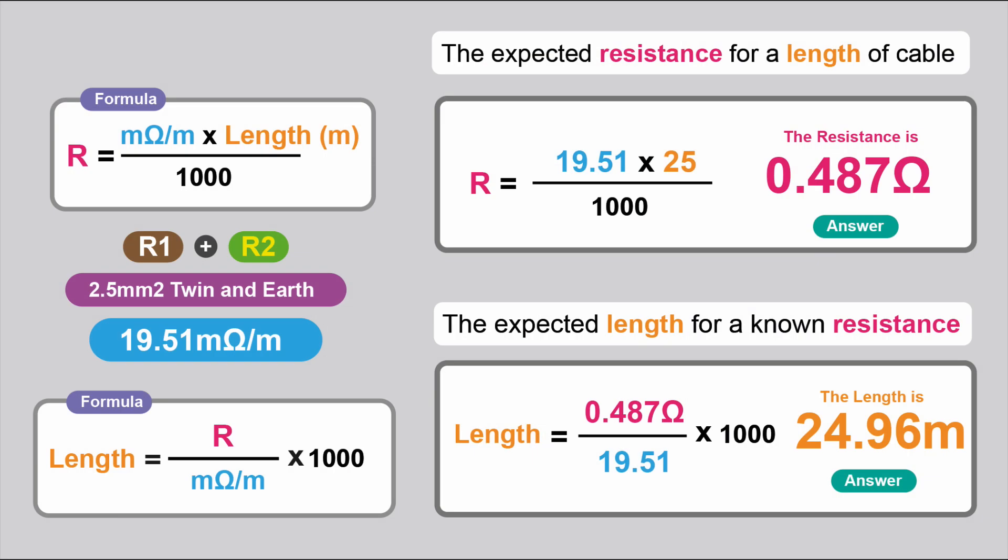So we've been working out the expected resistance for a length of cable. But as mentioned before, we can work out the expected length for a known resistance. It's just a little bit of transposition of the formula. So we're going to do the R1 plus R2 for 2.5 millimetre squared twin-and-earth cable, and that's 19.51 milliohms per metre for the R1 plus R2.